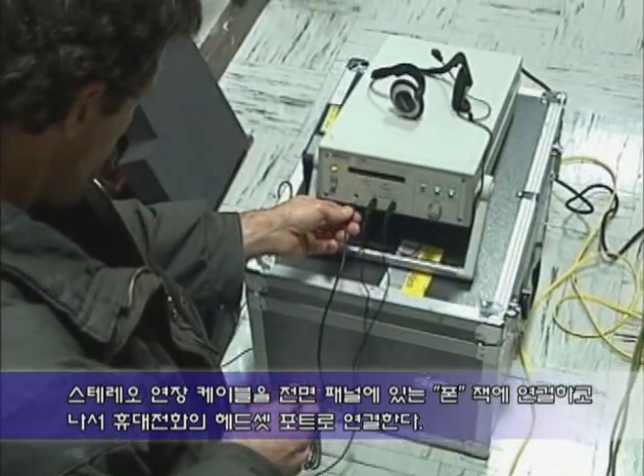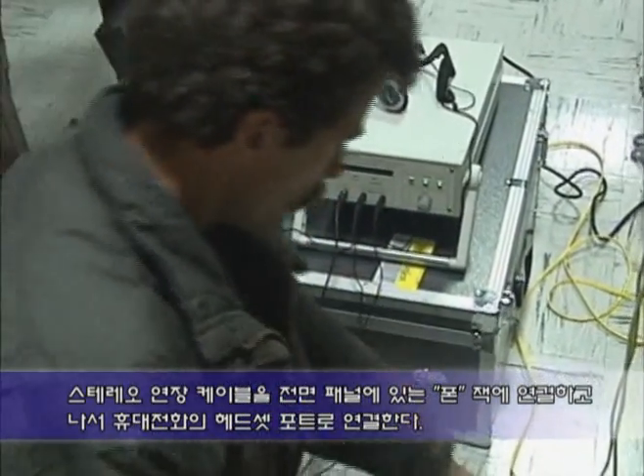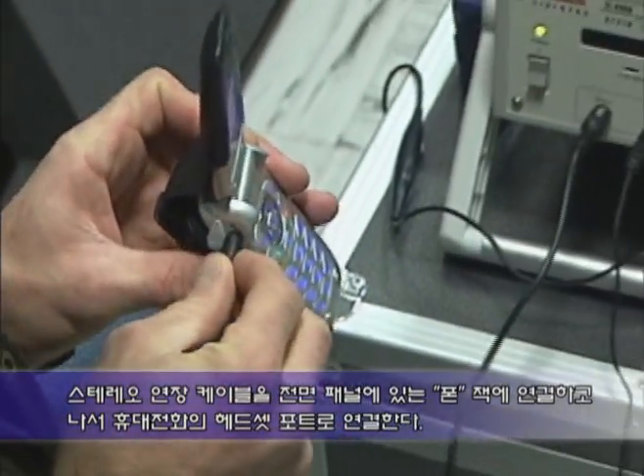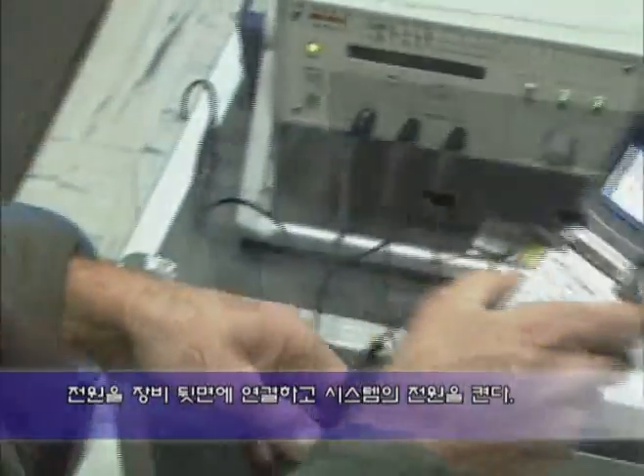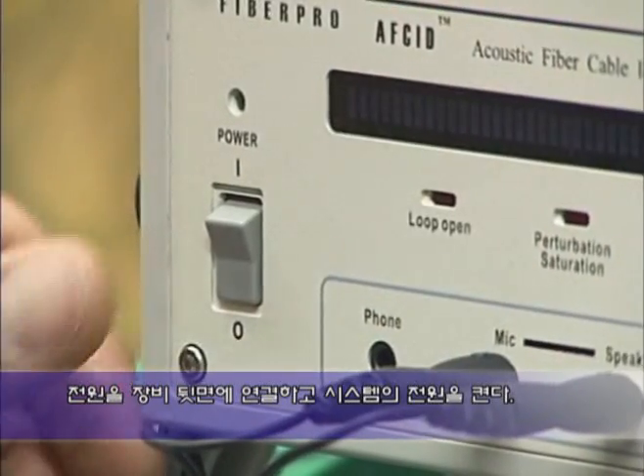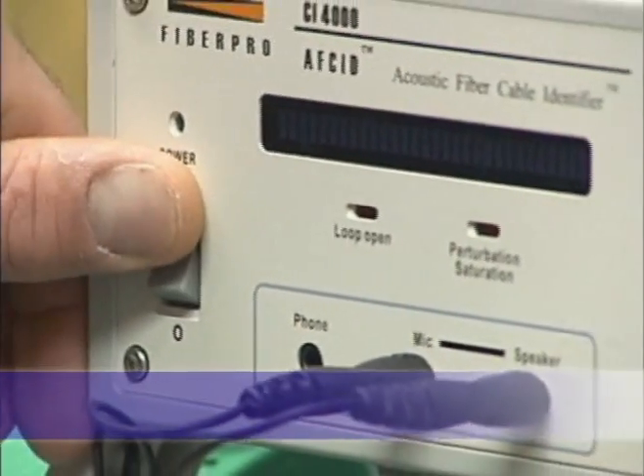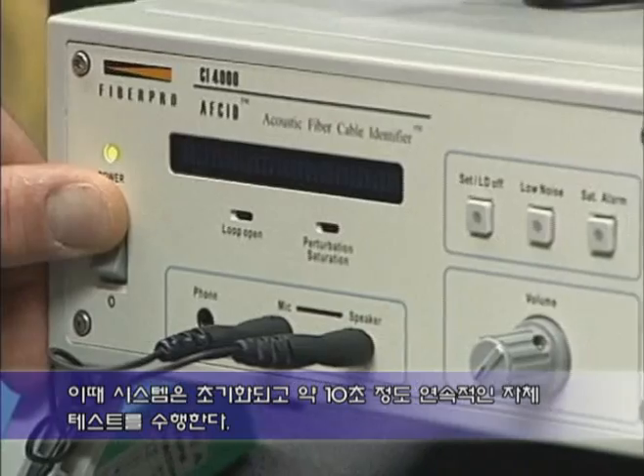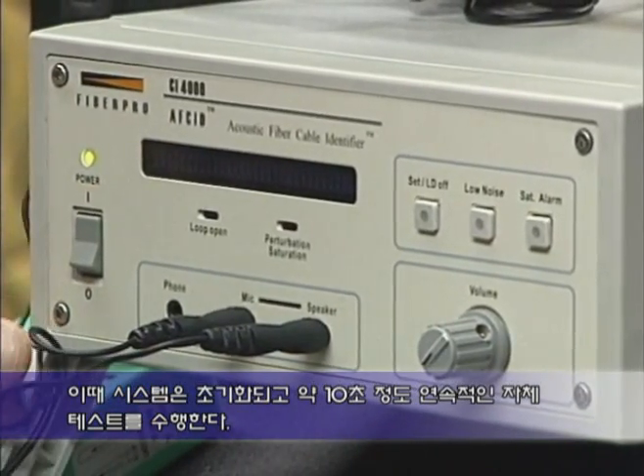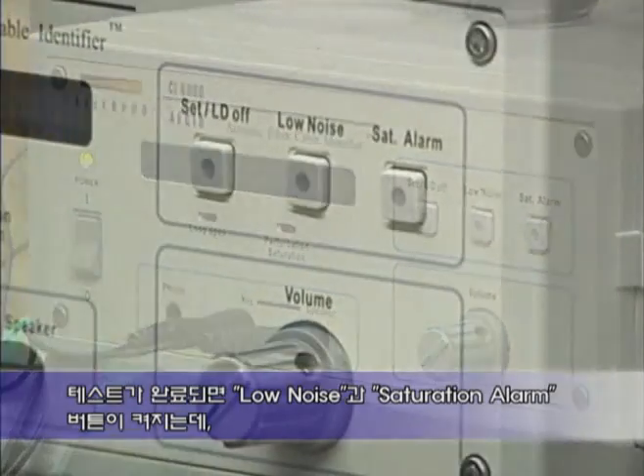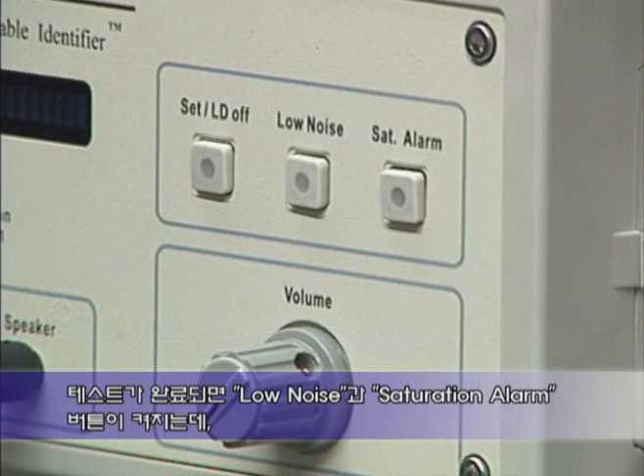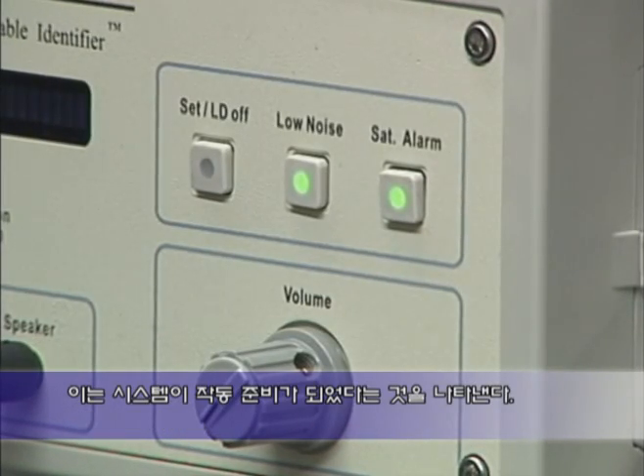Connect the stereo extension cable to the phone jack on the front panel and then to the headset port of a cellular telephone. Connect the power cord to the rear of the instrument and switch the instrument on. The instrument will initialize and perform a series of self-tests which take approximately 10 seconds. When complete, the low noise and the saturation alarm push buttons will illuminate, indicating the instrument is ready for operation.